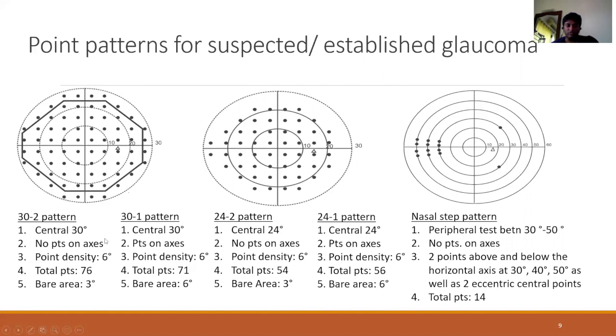In the 30-2 pattern, the central 30 degrees are covered with no points on the horizontal or vertical axis. The point density, that is the separation between two consecutive points, is 6 degrees. The total number of points covered is 76. The bare area around fixation is 3 degrees. The 30-1 pattern is exactly the same except that points are aligned along the horizontal and vertical axis, and because of that alignment the central bare area increases to 6 degrees.